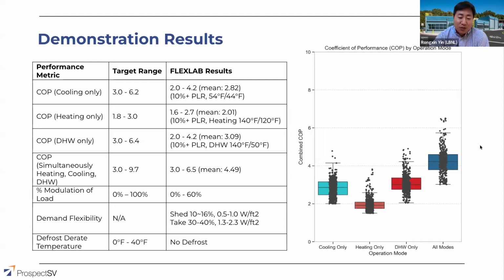Considering the load shed during the on-peak period, the load can be reduced by 0.5 to 1.0 watt per square foot. We do have a storage tank, so if you lower the setpoint during the daytime, which is part load, part mid-peak, the load take metric is roughly between 1.3 and 2.3 watts per square foot. The heat pump is capable of flexibility in both directions, up and down, compared to a traditional air-cooled chiller or natural gas boiler. With those, you can barely do anything for load flexibility in the heating season. And let's move on to the next slide.